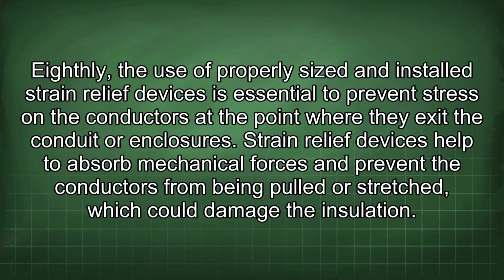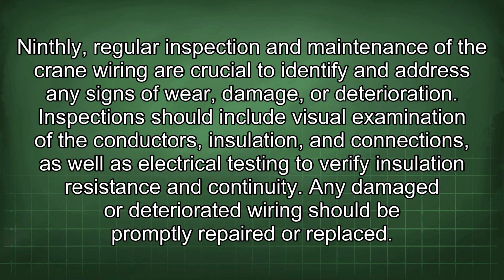Ninthly, regular inspection and maintenance of the crane wiring are crucial to identify and address any signs of wear, damage, or deterioration. Inspection should include visual examination of the conductors, insulation, and connections, as well as electrical testing to verify insulation resistance and continuity. Any damaged or deteriorated wiring should be promptly repaired or replaced.